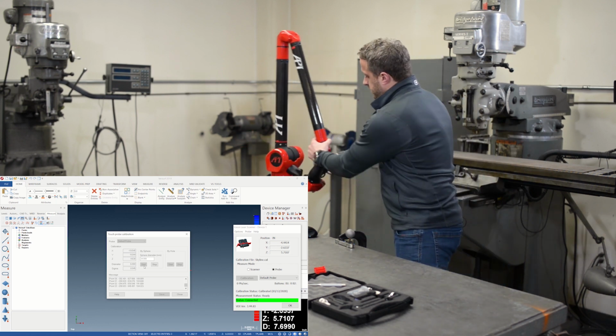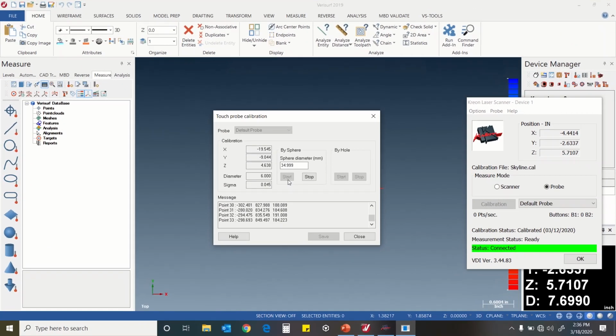And when you're done, you're going to hit stop, and it's going to give us our diameter. We have 35.013, so roughly 14 microns above the nominal diameter of the calibration sphere, so it was good. So I'm going to hit save, close.